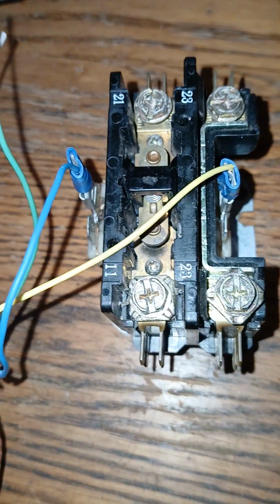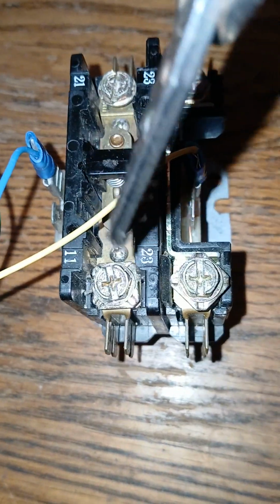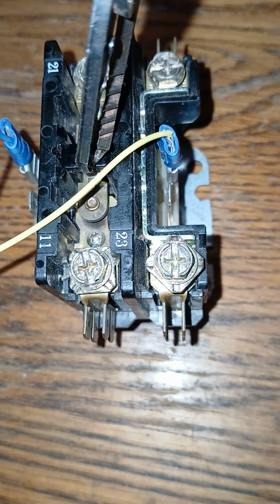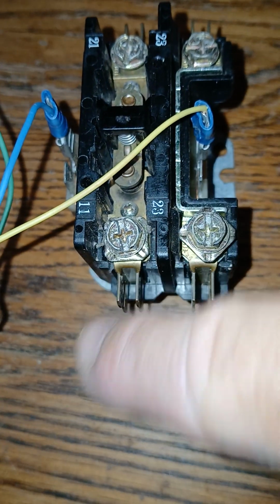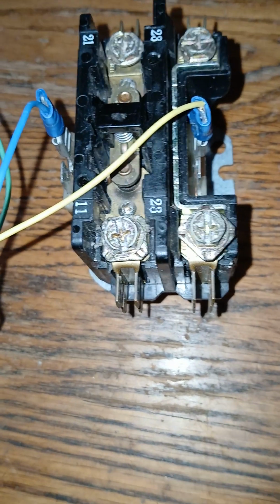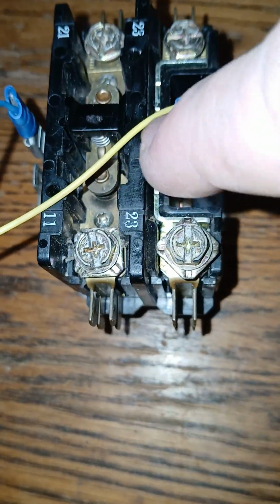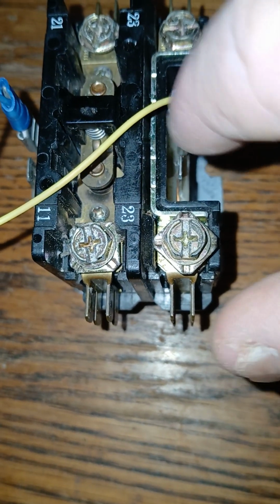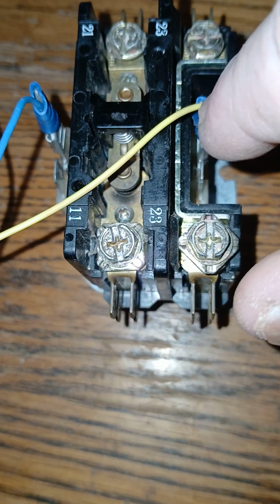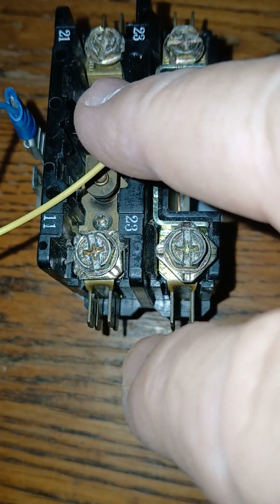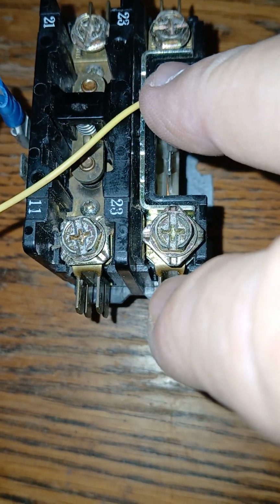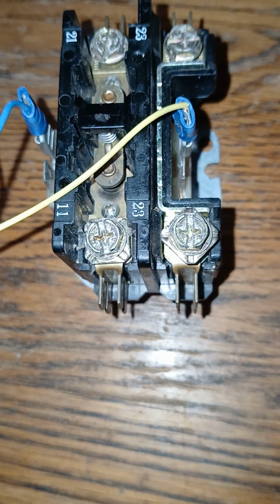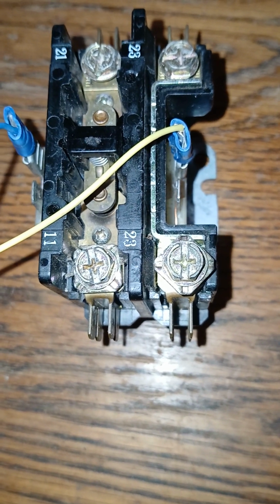So now the hot and the common, if the thermostat energizes 24 volts, it should pull this in, and once it pulls this in, it creates a magnetic field, and this magnetic field will convey the electricity from this side to this side. So again, this is the low voltage side, as one can see. And again, if the HVAC gurus can put what would be the best spade connector. Now, there is another way to do this. One could put the spade connector onto a wire, and some of them may have it like a stranded wire, so it's more bendable than the solid wire, and do it this way. I'm not sure that it makes that much difference. If the HVAC guys can add this, that would be good.